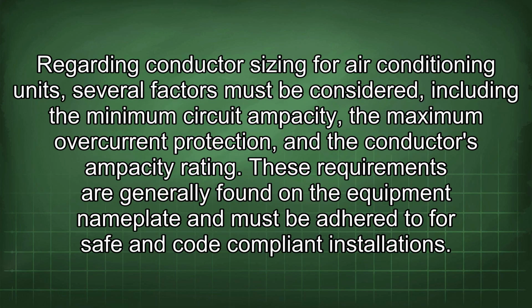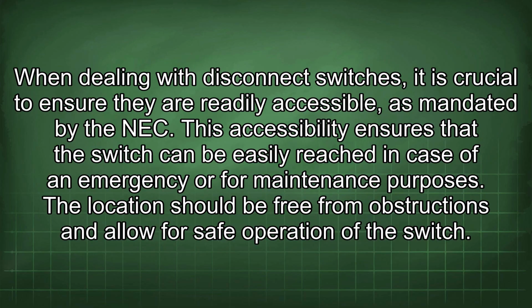Regarding conductor sizing for air conditioning units, several factors must be considered, including the minimum circuit ampacity, the maximum overcurrent protection, and the conductor's ampacity rating. These requirements are generally found on the equipment nameplate and must be adhered to for a safe and code-compliant installation. When dealing with disconnect switches, it is crucial to ensure they are readily accessible, as mandated by the NEC. This accessibility ensures that the switch can be easily reached in case of an emergency or for maintenance purposes. The location should be free from obstructions and allow for safe operation of the switch.